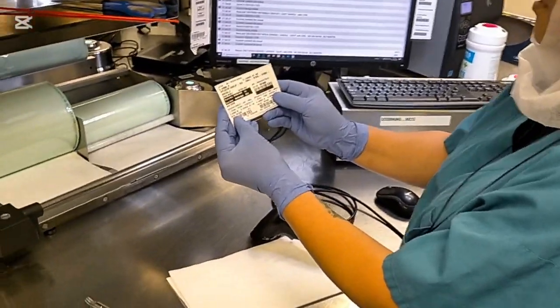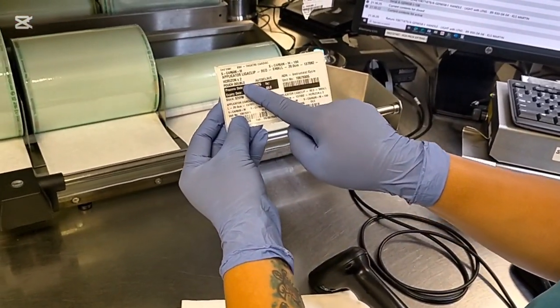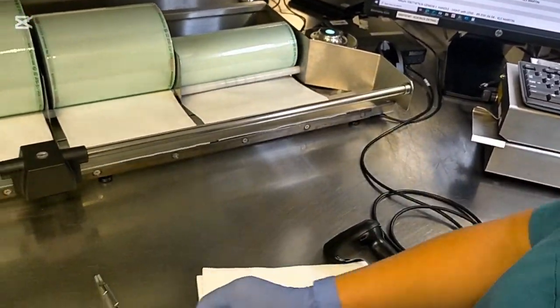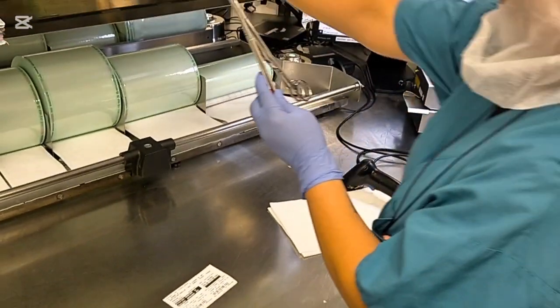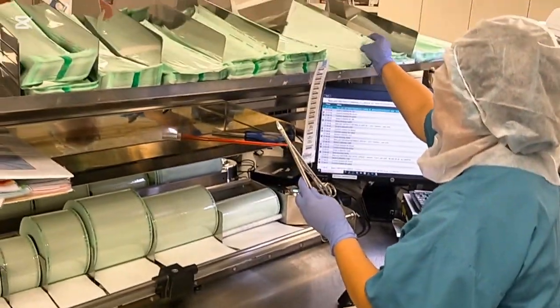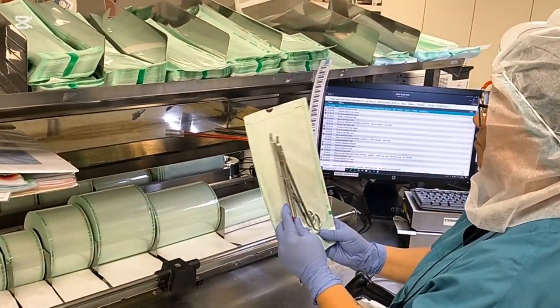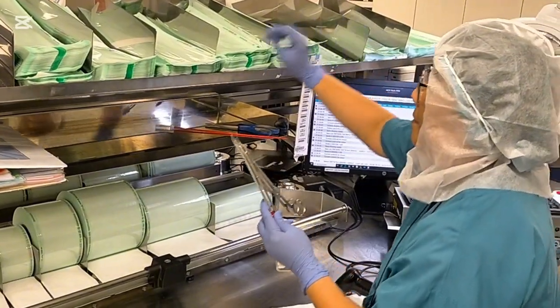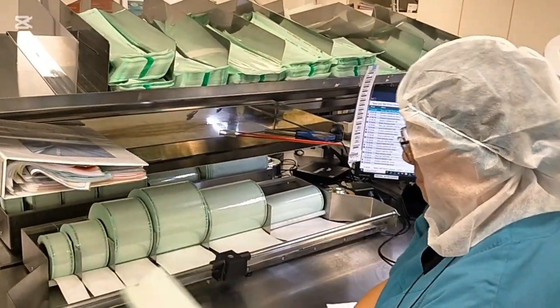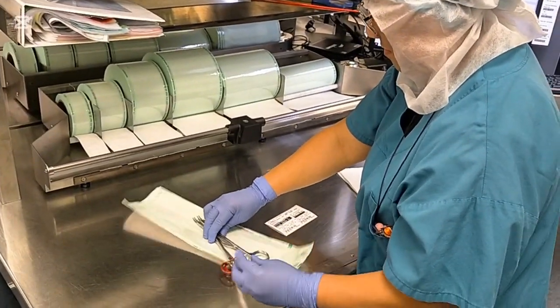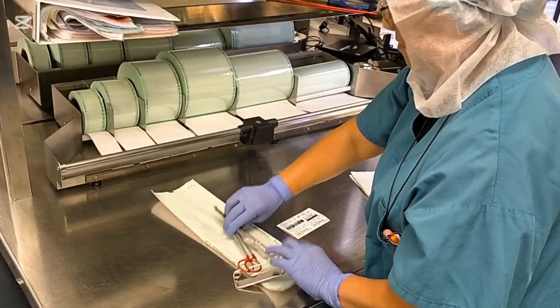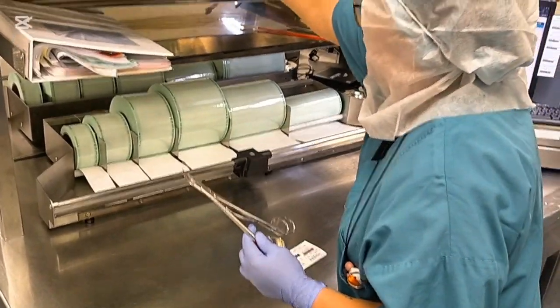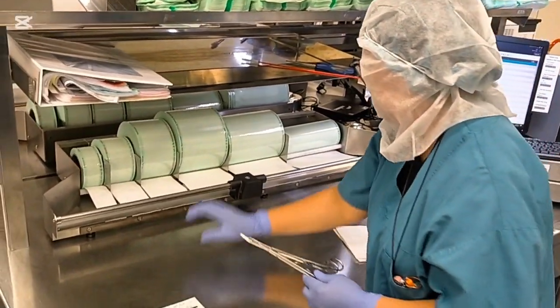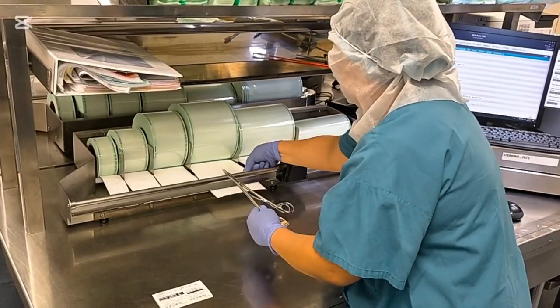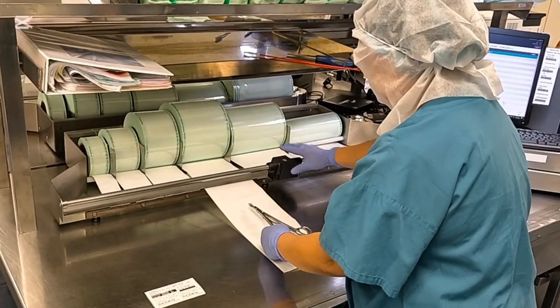Here, it will tell us whether we will use single or double pouching. In this case, it tells us to do double pouching. We will look for pre-cut pouch to match the size of our device. Remember, package should be filled to no more than 3/4 of their length and minimum of 2 cm empty space around each instrument. Since we don't have available pre-cut to fit in our device, we will then use our reel.